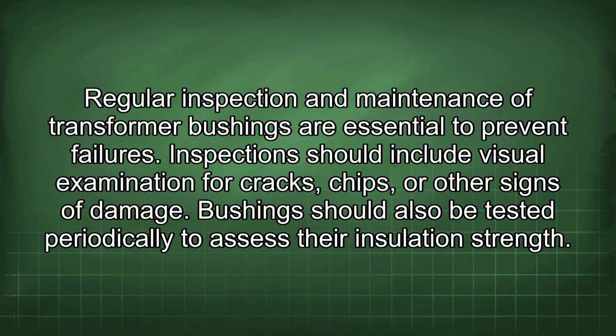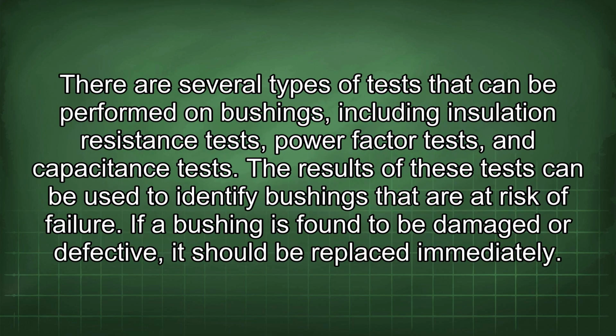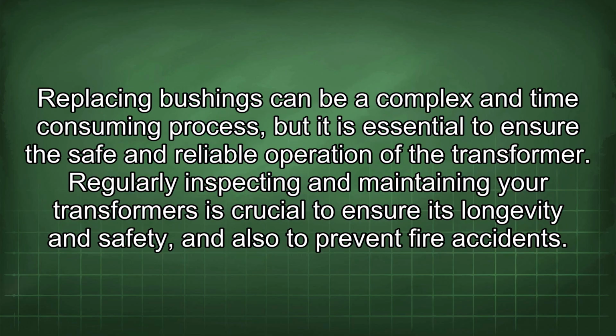Inspection should include visual examination for cracks, chips, or other signs of damage. Bushings should also be tested periodically to assess their insulation strength. There are several types of tests that can be performed on bushings, including insulation resistance tests, power factor tests, and capacitance tests. The results of these tests can be used to identify bushings that are at risk of failure. If a bushing is found to be damaged or defective, it should be replaced immediately. Replacing bushings can be a complex and time-consuming process, but it is essential to ensure the safe and reliable operation of the transformer.